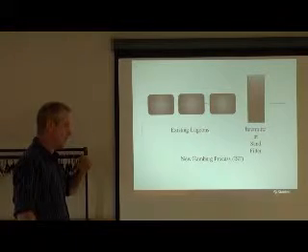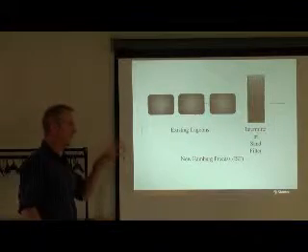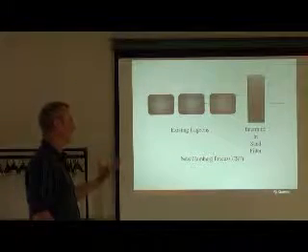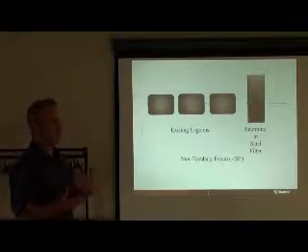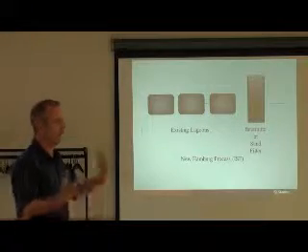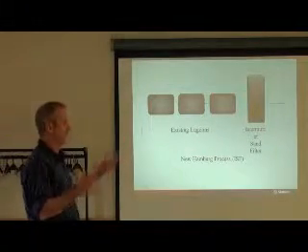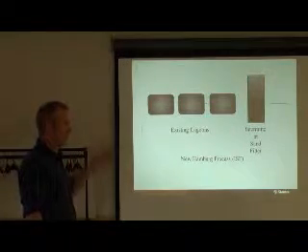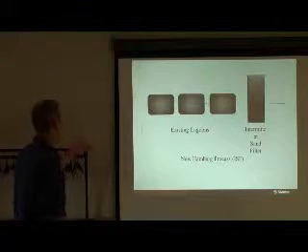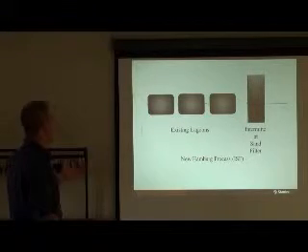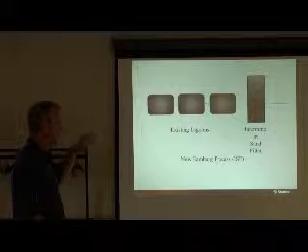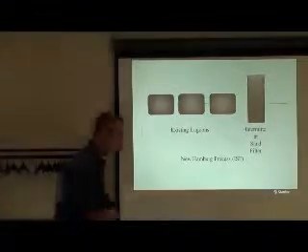Ontario. The problem you have with lagoons is they don't do ammonia treatment very well. The ammonia is toxic to aquatic life, so the Ministry of Environment sets limits on ammonia. One of the ways to deal with the ammonia is to use an intermittent sand filter at the end of a lagoon to get that ammonia knocked down before it goes out the effluent. So that's one of the options we're looking at.